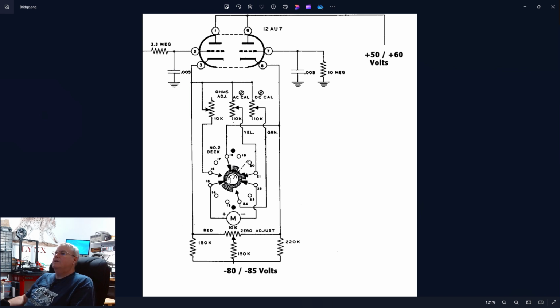Also, when doing AC, your adjustment controls are going to be different depending on if you're on DC, AC, or ohms. So this switch also picks up one leg of the meter from one of these pots. When we're in DC, it picks it up right here and routes it through the switch over to the positive. The other side comes down directly in, routes around to the negative side of the pot, and by doing that the meter can be switched polarity wise.